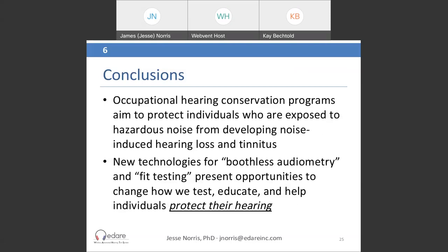Question: Is the additional attenuation achieved by active noise cancellation? No, it is achieved through passive attenuation. We made that decision in part because a regulation specifies that active noise cancellation cannot be used for achieving that additional attenuation in this context — there's concern over its impact on the test, as ANC can introduce artifact frequencies. The system is currently designed purely passive, and also for reliability reasons, similar to a sound booth.